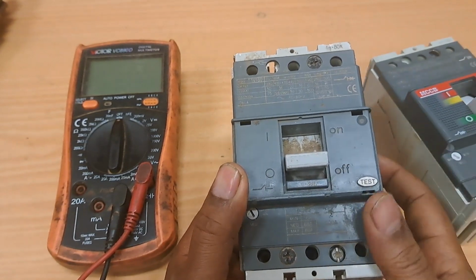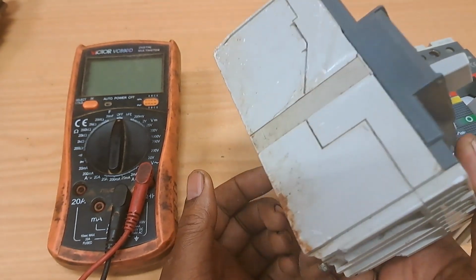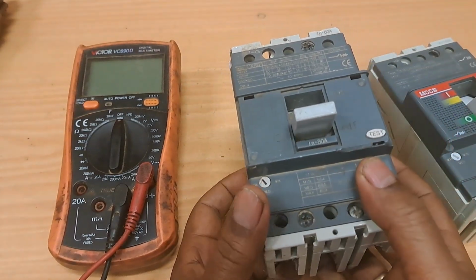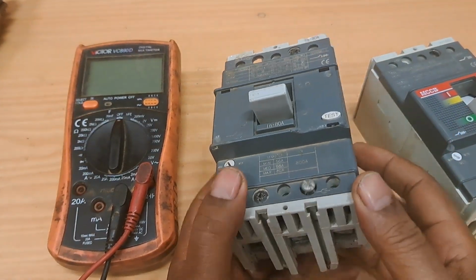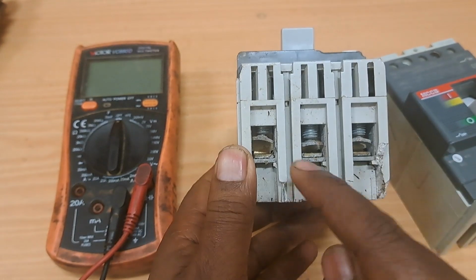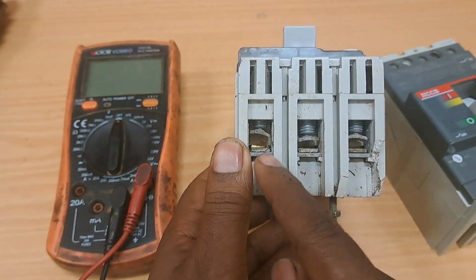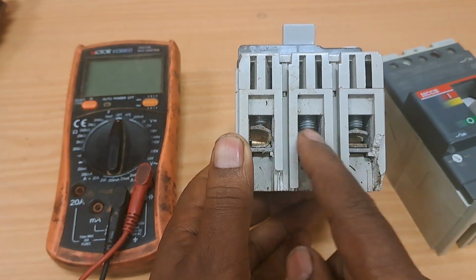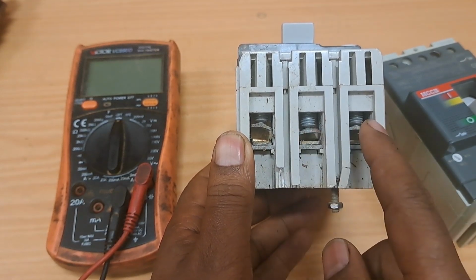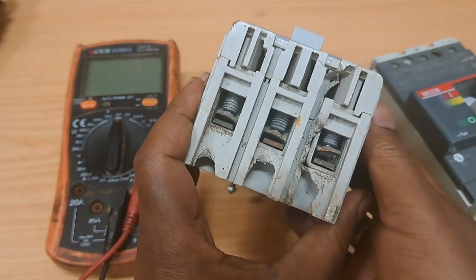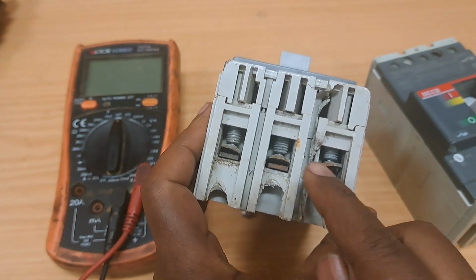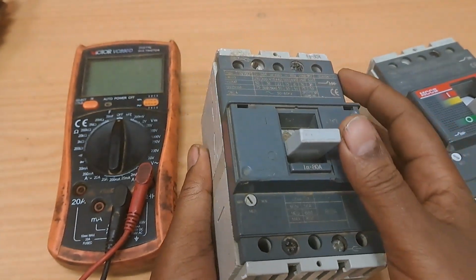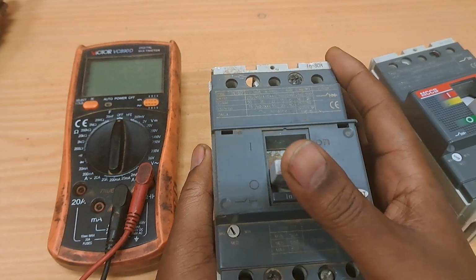Now, how do we inspect? Begin inspecting the operation of the circuit breaker first by visual inspection. Make sure that the contacts where terminals are going to be connected are clean, and make sure that all the screws are available, and look around for any corrosion or any type of rust. And then go ahead and see if the switch latches properly or not.